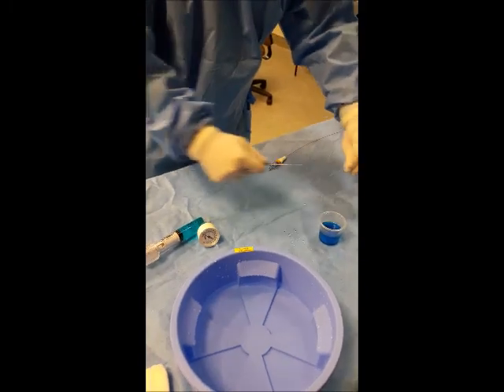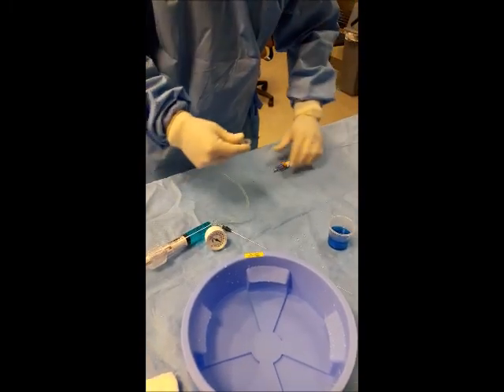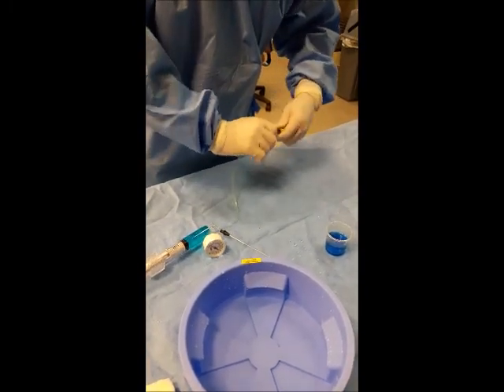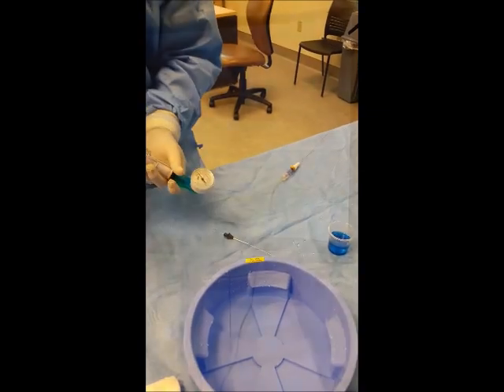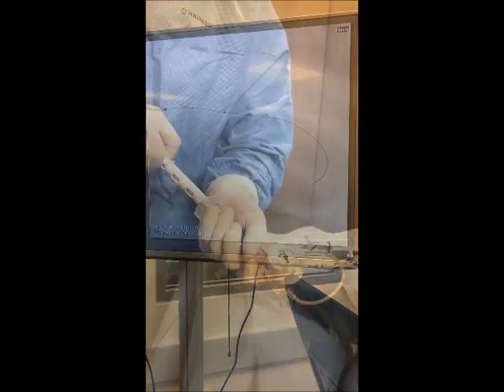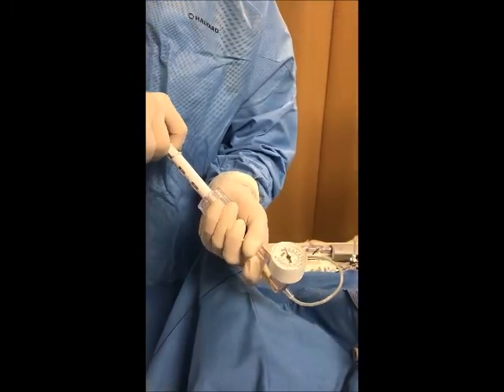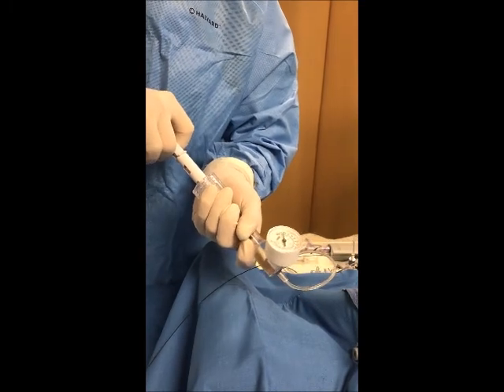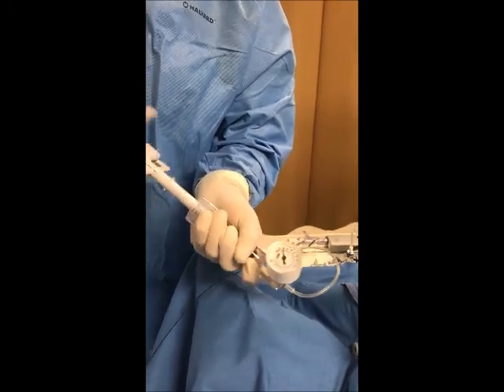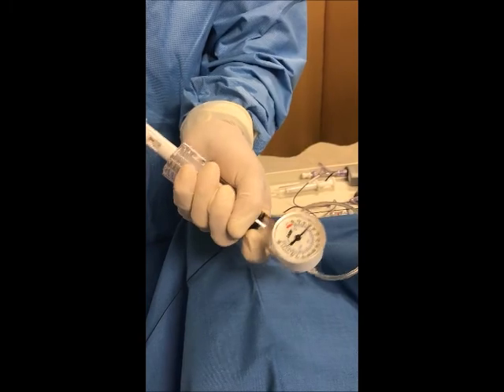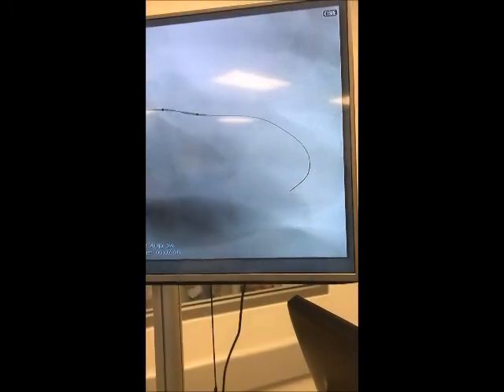Connect the indeflator to the balloon port. In a rail system, which is shown here, there is only one hub in which the indeflator can be connected. For over-the-wire balloons, the indeflator is connected to the side port. Connect the indeflator to the correct connection. If you're using a balloon, you can pull negative at this point to reduce the profile of the balloon. If you're using a balloon expandable stent, do not pull negative, as it can cause the stent to remove from the balloon placement. Once placement is confirmed, the physician will ask you to inflate the balloon.